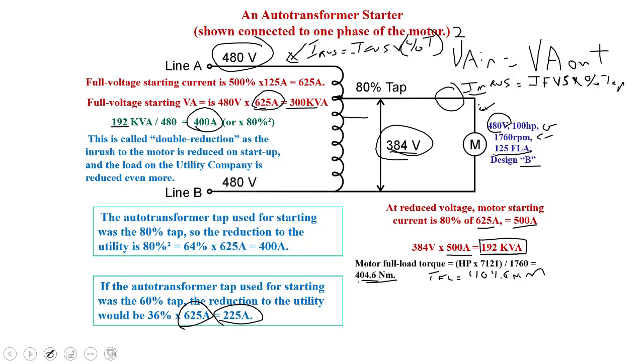Well, because it's a design B rotor, we're going to see about 150% of that during startup. It's going to produce 150% of its running torque during startup. So full voltage starting torque for this motor, 404.6 times 150%. So I could say torque full voltage start is equal to torque full load times 150%, if you want to write it out like a formula.